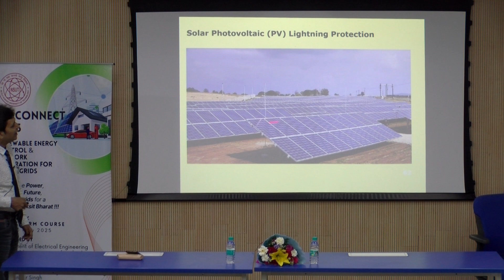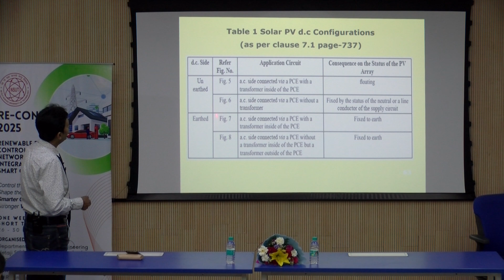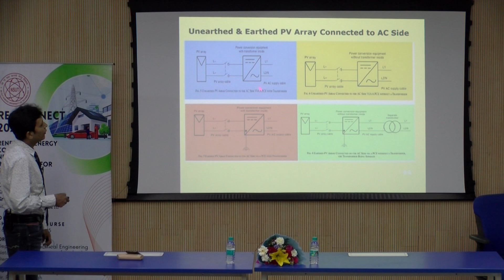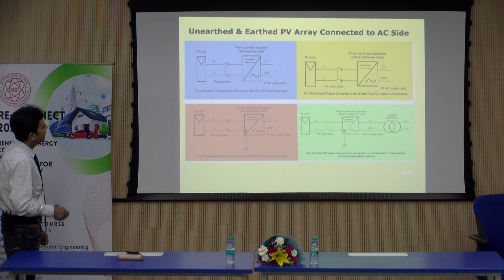This is how the lightning protections are provided based on the calculation and design. This is the NEC guidelines that gives guidance in clause number 7.1, page 737 of NEC 2023, on how to do proper earthing on the DC side. This picture depicts everything. You can refer to NEC 2023 to ensure how that earthing is to be done. These 4 figures are very important.